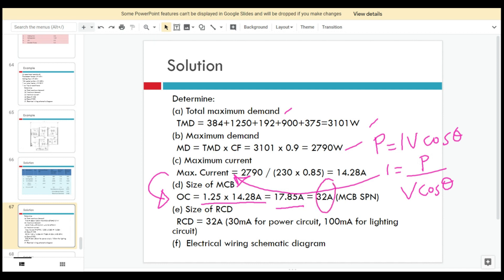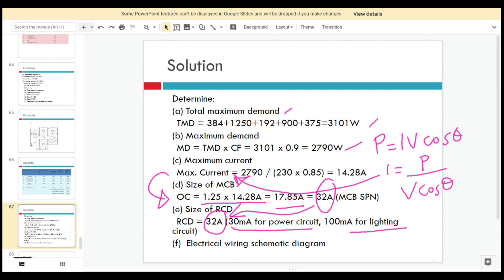For the RCD, it must be equivalent to or larger than the MCB, so you can directly choose 32 amps for the RCD or RCCB as well. The sensitivity is 30 milliamps for the power circuit and 100 milliamps for the lighting circuit. You also have to consider additional protection for the water heater.